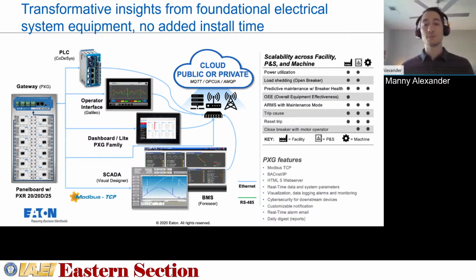So I mentioned the built-in communications on a couple slides, and these Power Defense breakers with the PXR Power Xpert Release trip units have built-in Modbus communications because all of these trip units are collecting an immense amount of data. And like I said earlier, you want to be able to communicate that to something in order to create action, right? And to use that data.